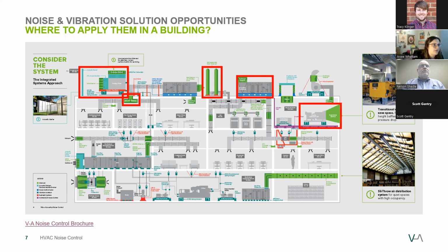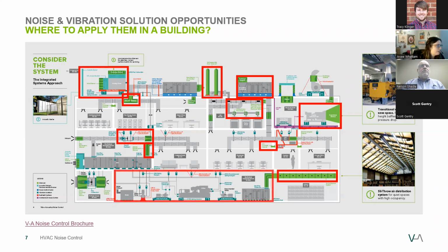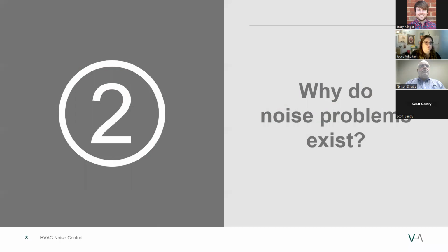Over here on the right, you can see a generator with a transitional discharge silencer on vibration isolation and on a floating floor. We've got some fume hood silencers in the lab. There's some just straight silencers on a duct on a suspended piece of equipment. Elbow silencer here with mold block in the mechanical room. We've got a crosstalk silencer between two rooms. There's the Sil-Throw distribution system in the library at the bottom right. And we've got the mechanical room here just with various vibration isolation and noise control products on all the equipment. And finally, some circular silencers on an axial fan. So that's just a quick summary there, a good tool to use, but let's ask ourselves, why do noise problems exist?